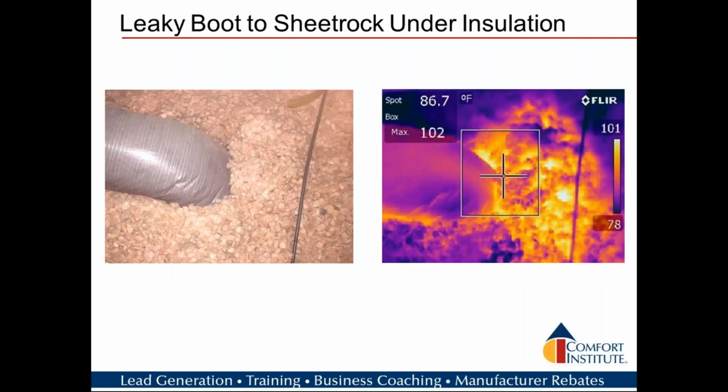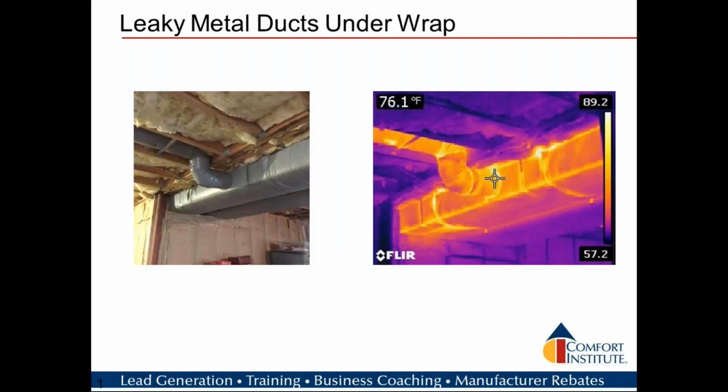Now, what about that boot that's under the sheetrock, or under the insulation, buried into the sheetrock up there? How do you spot that, look for leakage in it? With the infrared, it makes it very easy for me to see that we have an issue here, and I can have a tech take pictures of it, and we can bring it to the attention of the homeowner, turn this into something more, get in there and find out what's going on. Even under insulation, whether in a crawl space or up in an attic, infrared technology can help us determine whether or not we have problems. I won't say it'd be the only thing that sells it for us, but at least it shows there are concerns, and we can turn it into something by doing some further diagnostics.